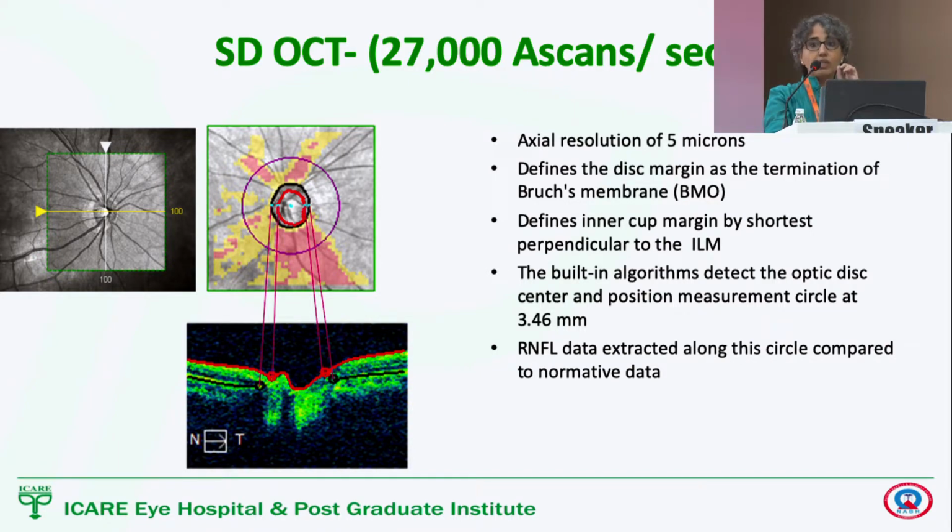And it's important that when you look at a printout and you've seen the eye, you check that the detection the system is doing is done correctly, because all the calculations are going to be based on your structural detection of where the optic nerve head lies. And that is an important training you also give your operator.